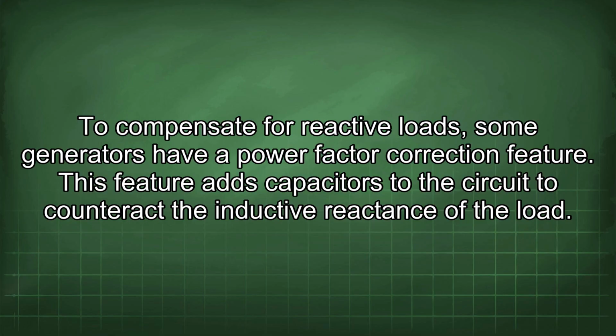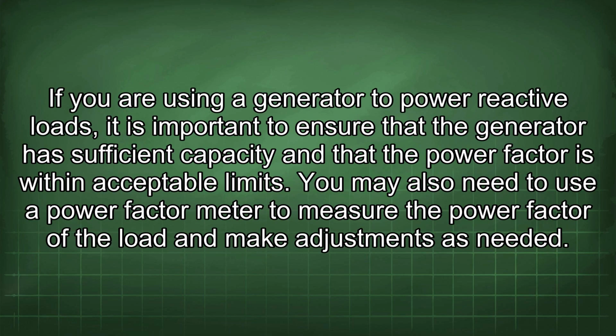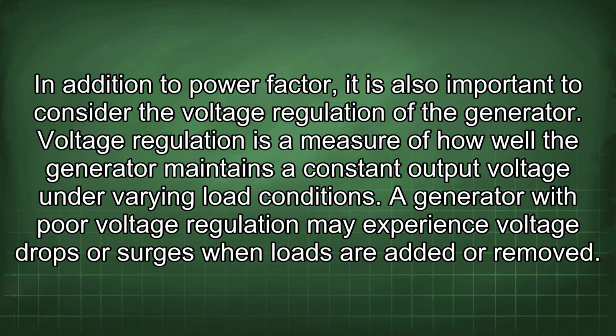This feature adds capacitors to the circuit to counteract the inductive reactance of the load. If you are using a generator to power reactive loads, it is important to ensure that the generator has sufficient capacity and that the power factor is within acceptable limits. You may also need to use a power factor meter to measure the power factor of the load and make adjustments as needed. In addition to power factor, it is also important to consider the voltage regulation of the generator.